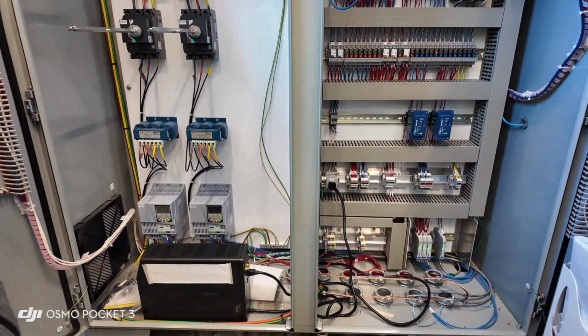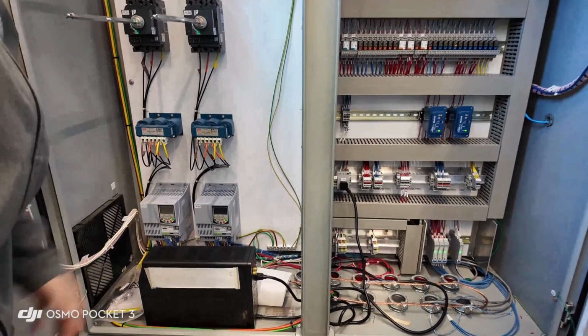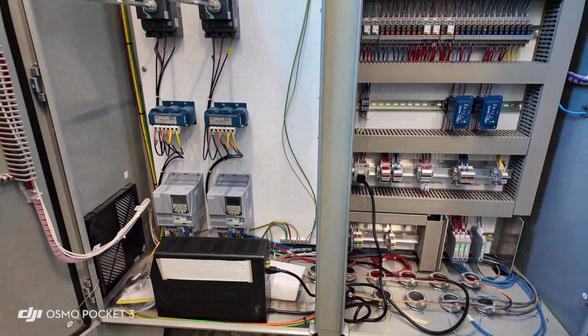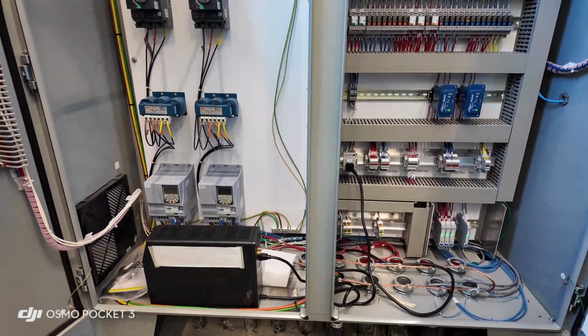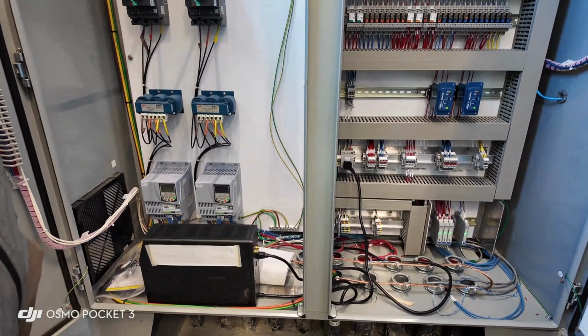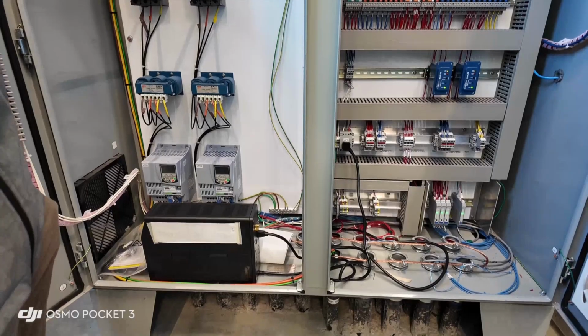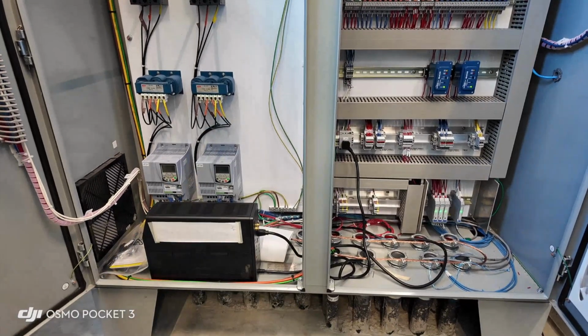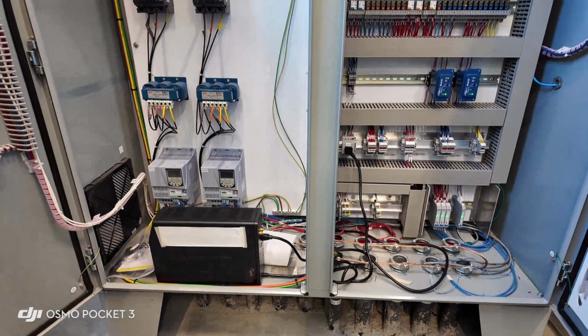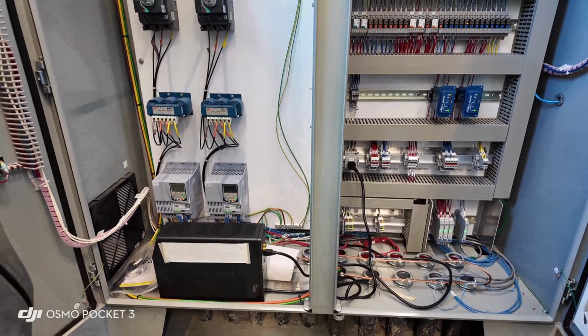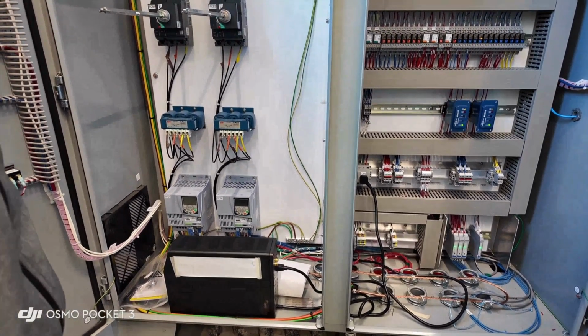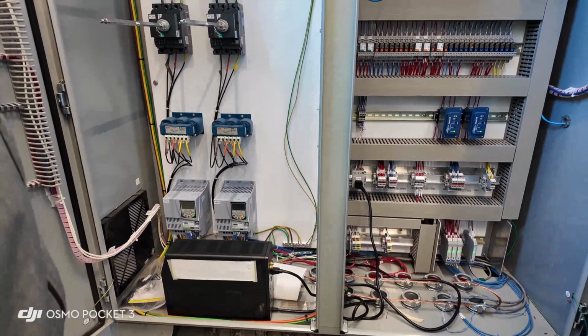Just protect them. And then down here we have our CFW 500 series general purpose OEM drives. They are rated, I think, for 10 horsepower. These are 7.5 horsepower, so you have some room in case they have to increase the pumps or anything like that in the future. And they're rated for up to 14 amps heavy duty. So that's like continual run. So it's pretty good drives.